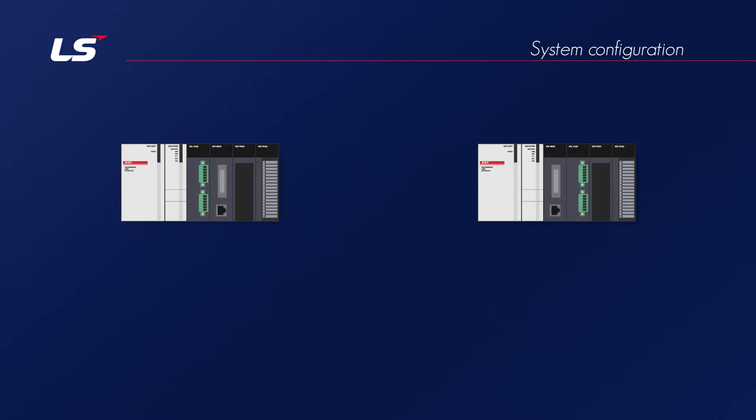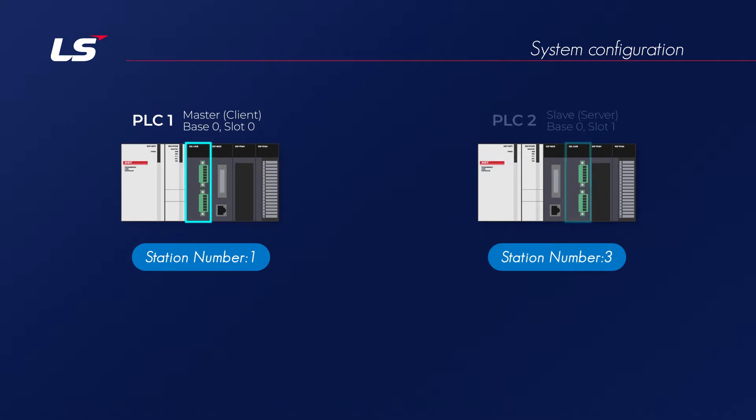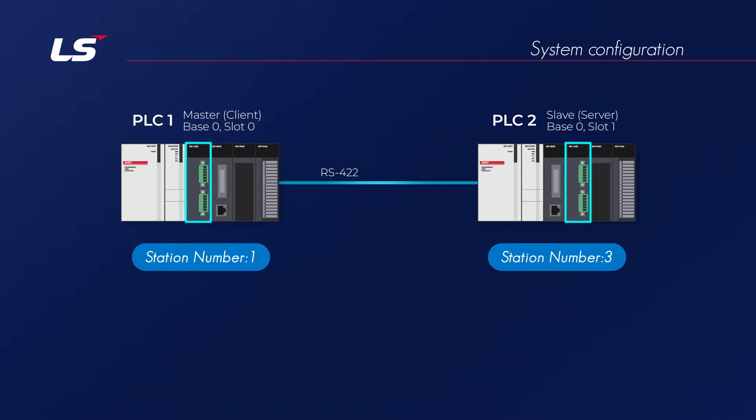The XG5000 program will be used to set the communication settings for exchanging data between XGT PLCs. PLC of station number 1 will be operated as master, and PLC of station number 3 will be operated as slave. These two PLCs use the RS422 communication method and will be configured as a system that transmits or receives data using XGT protocol.